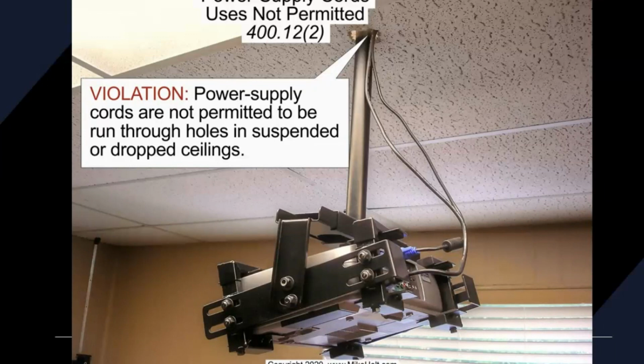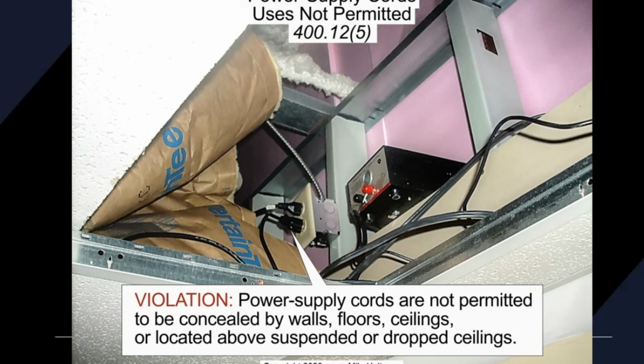We are not allowed to put cords above suspended ceilings. You see this all the time. This is something that, as an inspector, I failed a lot. At bars, dentist's offices, they'll put TVs up in the corner. I mean, just about every place. People use it for show window lighting, outlets, things of that nature. That's 400.12. So this picture is a violation, and you see it all the time. But you are not allowed to do that.